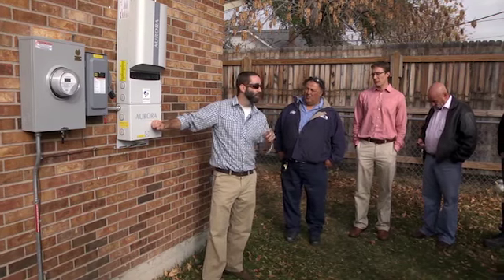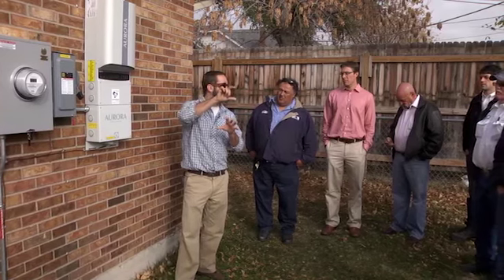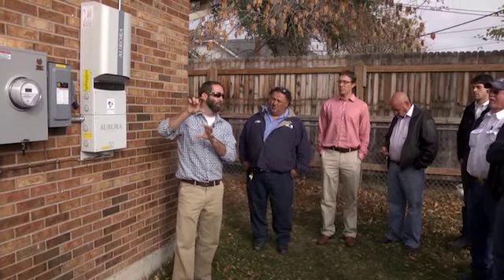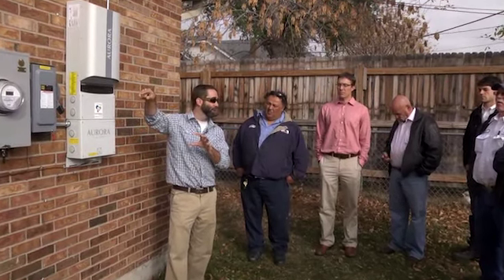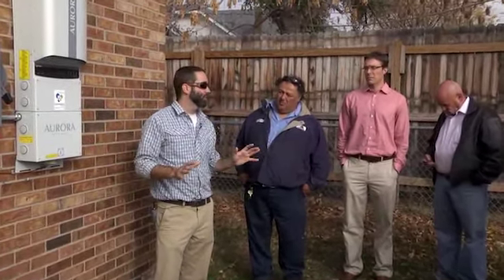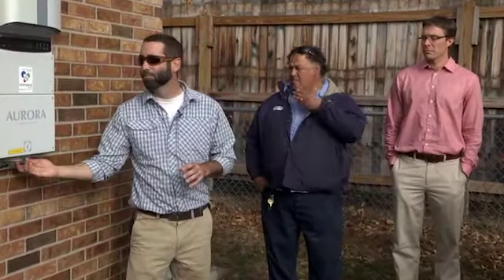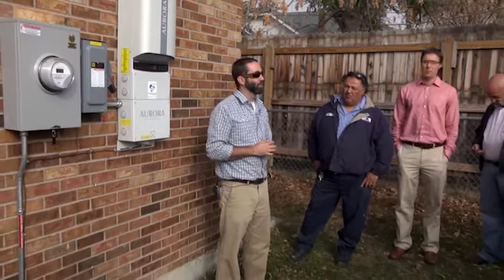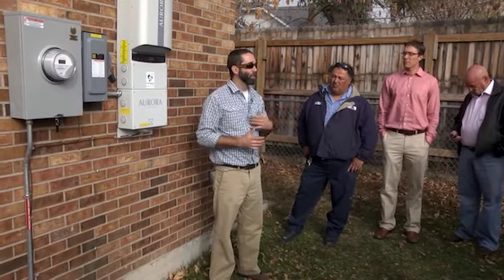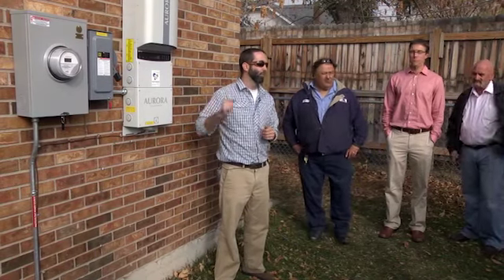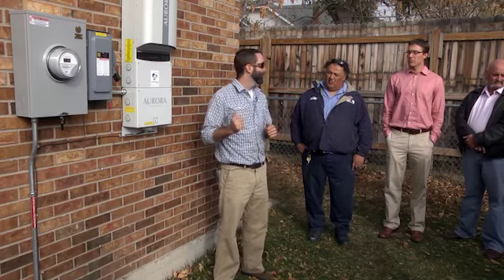You'll still be protected if you're working in the panel because the protection is the main breaker. But in this case, we're interconnected into the existing electrical system above the main breaker in that box, so it stays live. Best practice, whenever you walk on site to do any electrical work, go ahead, turn both the AC and the DC disconnect off on the solar, turn the main breaker off for the unit, and you are isolated from any electrical. Now, is that as far as changing your outlets and switches also? The question was whether or not you should follow that same procedure if you're changing lights and outlets as well. I would consider that best practice, yes. You should turn off the main breaker for the unit, turn off the solar. Once you're done, remember to turn the main breaker for the power back on, turn the solar back on, and walk away.